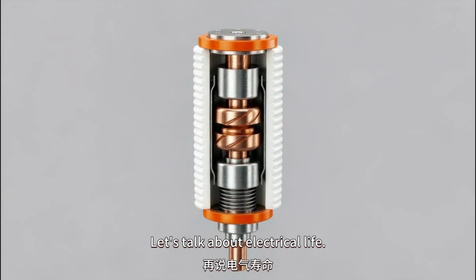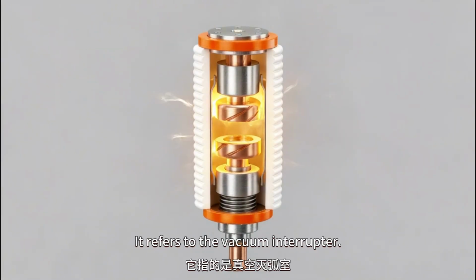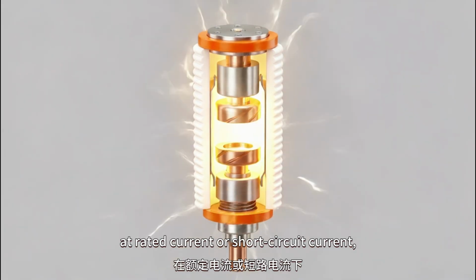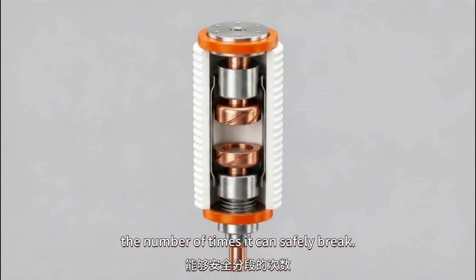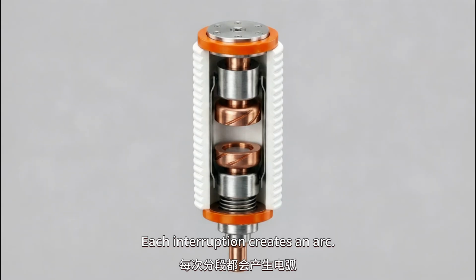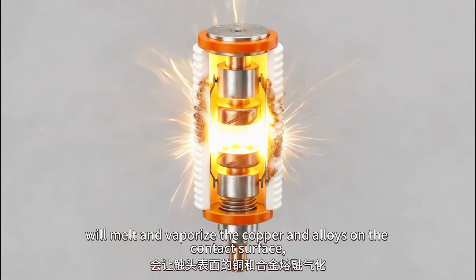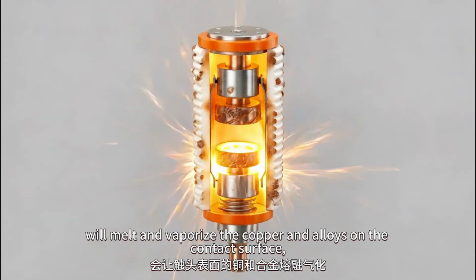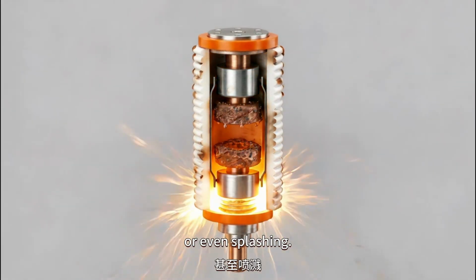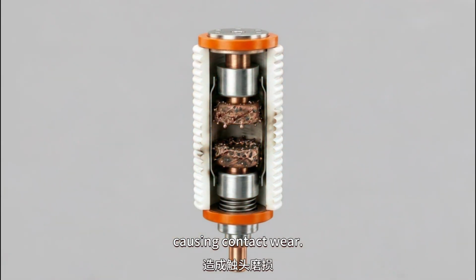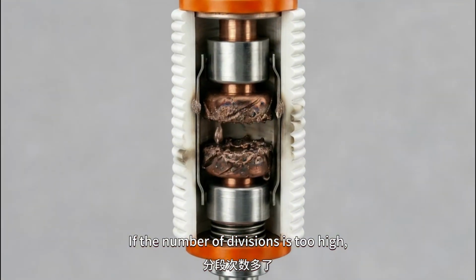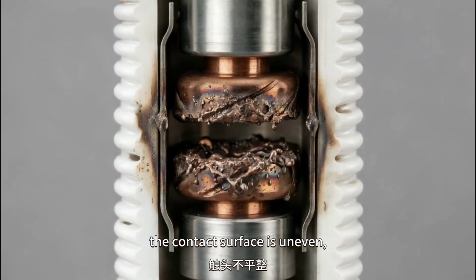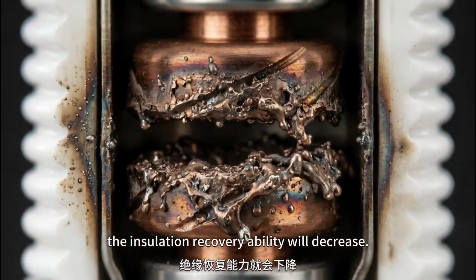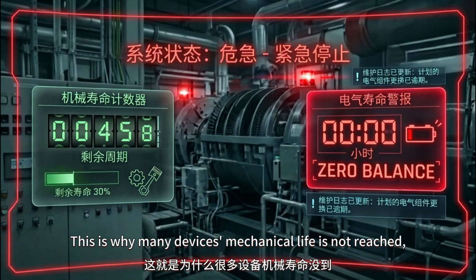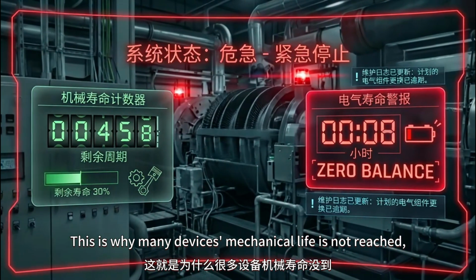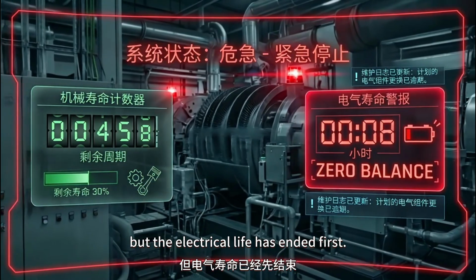Let's talk about electrical life. It refers to the number of times the vacuum interrupter can safely break at rated current or short circuit current. Each interruption creates an arc. High temperature will melt and vaporize the copper and alloys on the contact surface, or even cause splashing, causing contact wear. If the number of interruptions is too high, the insulation recovery ability will decrease. The contact surface becomes uneven. Therefore, this is why in many devices the mechanical life is not reached, but the electrical life has ended first.